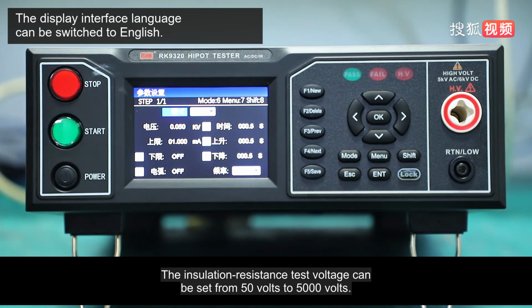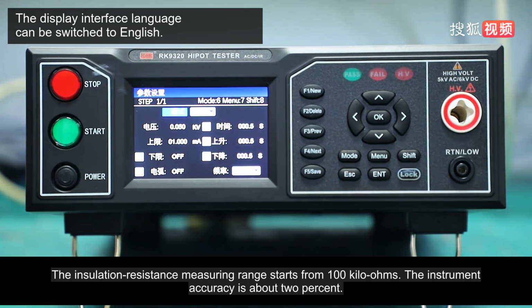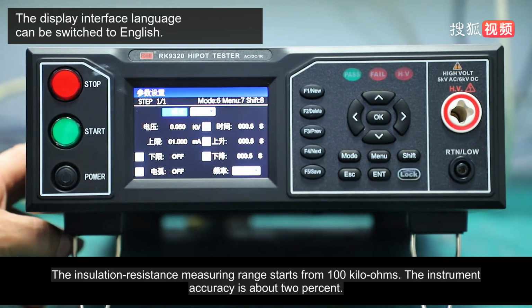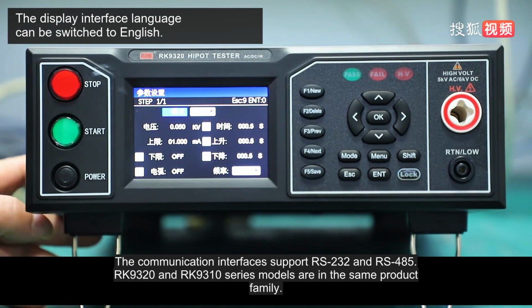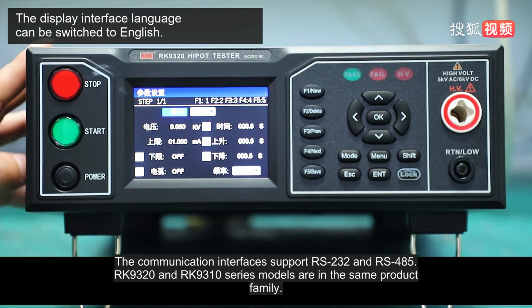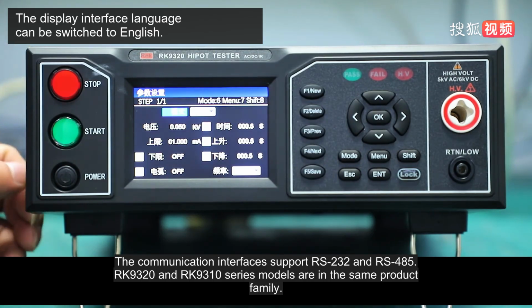The insulation resistance test voltage can be set from 50 volts to 5,000 volts. The insulation resistance measuring range starts from 100 kiloohms. The instrument accuracy is about 2%. The communication interfaces support RS-232 and RS-485.